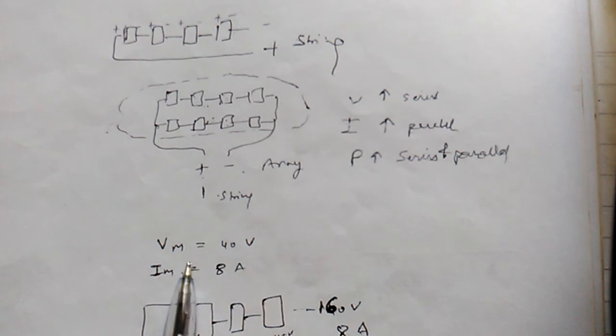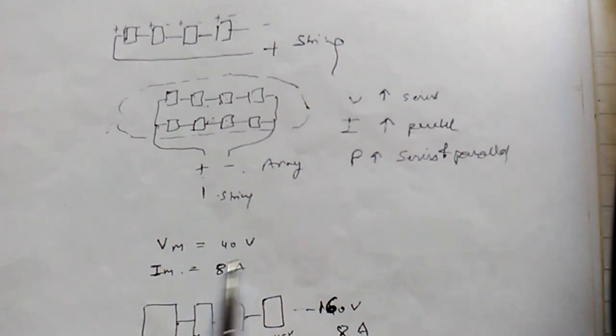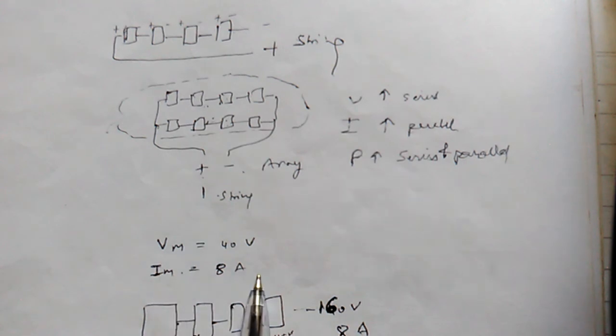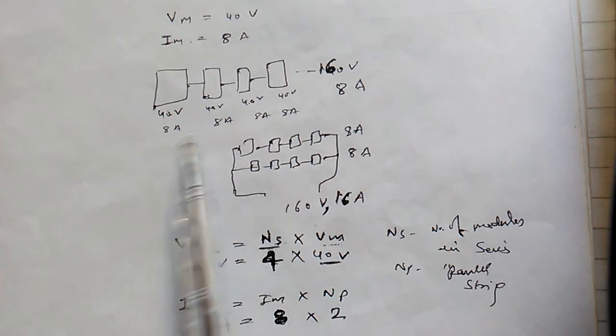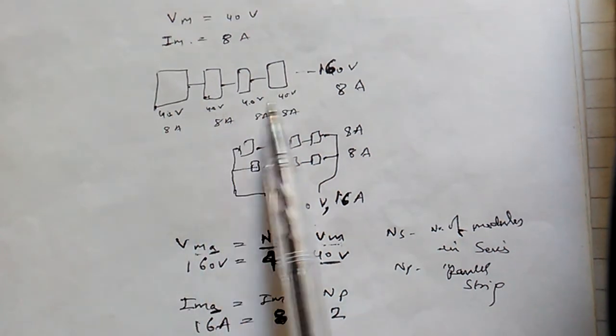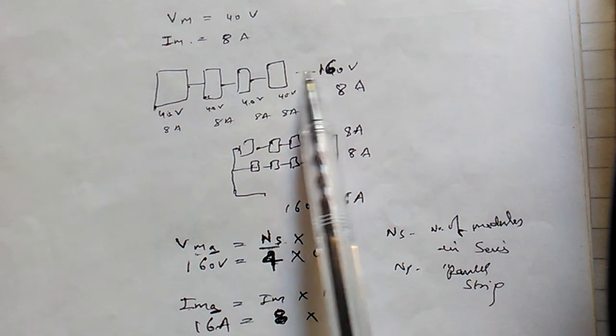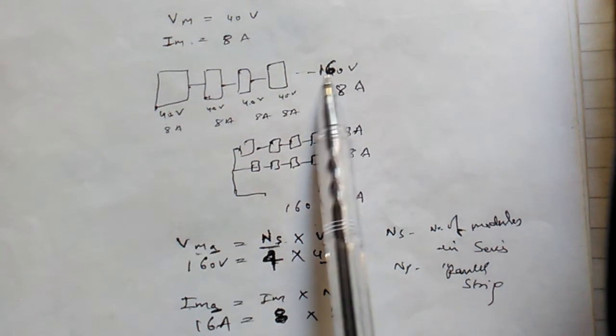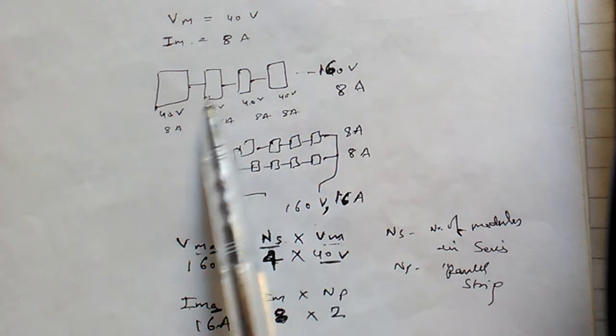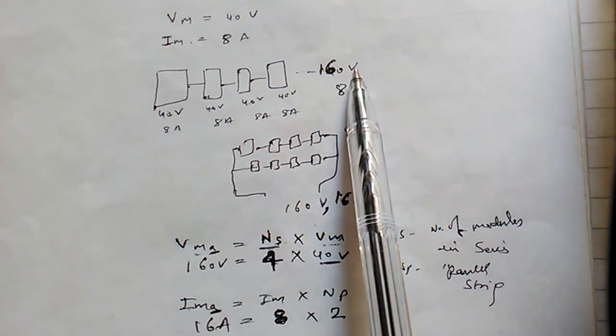The module parameters are: Vm (voltage at maximum power point) = 40 volts and Im (current at maximum power point) = 8 ampere, as mentioned on the module. If four modules are connected in series — 40V, 40V, 40V, 40V — the string output voltage is 160 volts because voltages add in series.